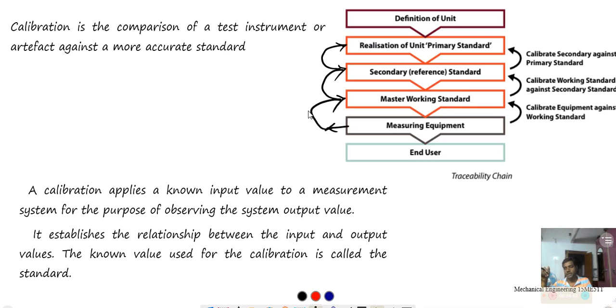How to calibrate? If I want to calibrate a scale which is on the shop floor, imagine it's a weighing scale, how do I calibrate it? I'm going to bring a lab standard, 1 kg of standard physical variable, and put it on the weighing scale. If it shows 1 kg, then that equipment is right. Every time I am going to measure n number of times, and n number of times it should indicate 1 kg only.